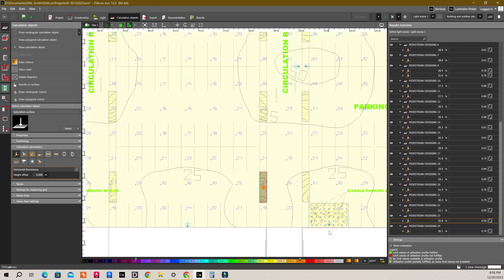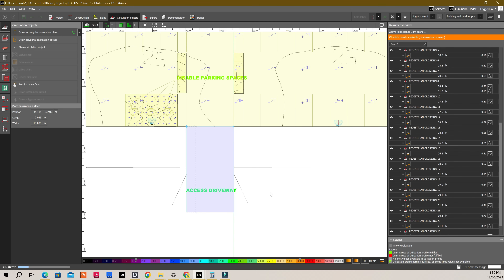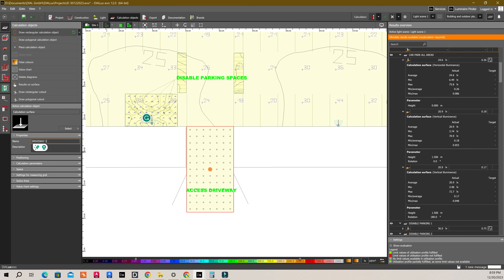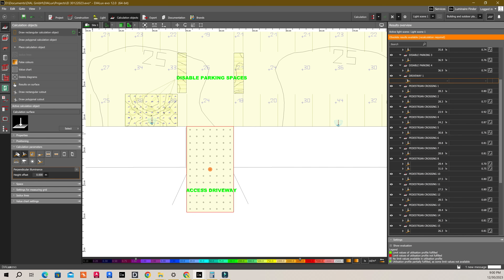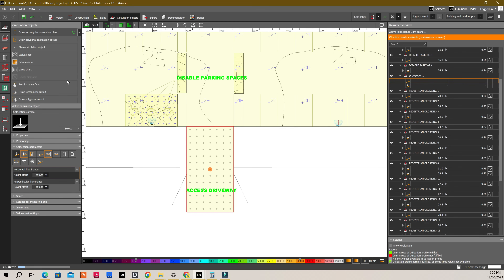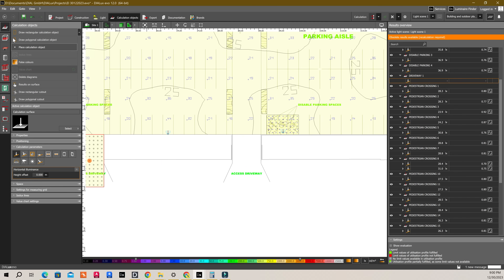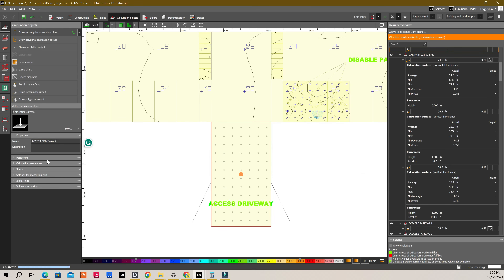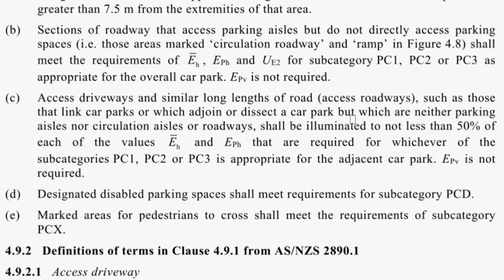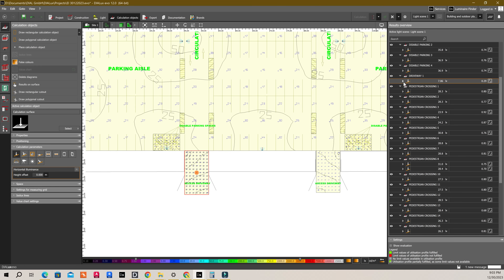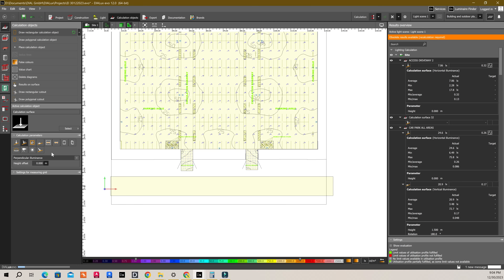Now, I am going to draw a rectangular calculation object for the access driveway — we need to do this as well. Draw this calculation object and rename it to 'driveway 1'. We need just horizontal lux values and don't have to worry about vertical here. Add a value chart as well — make sure you don't forget this, it's important. Do the same for access driveway 2 as well. For access driveways, we have to get 50% of the horizontal average and point lux value of the subcategory. For PC1, we have an average of 14 and minimum of 3. The average is greater than 50% of 14, which is 7 — so that is fine. The minimum point lux level is good as well, and same for driveway 2. So this is complying.